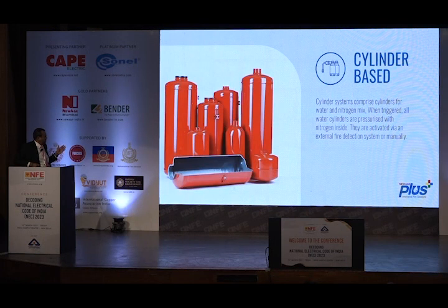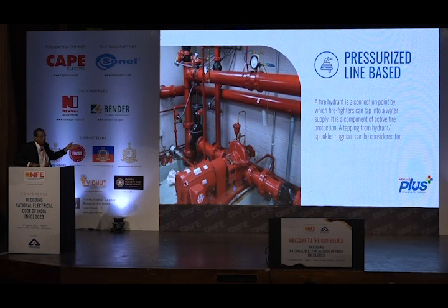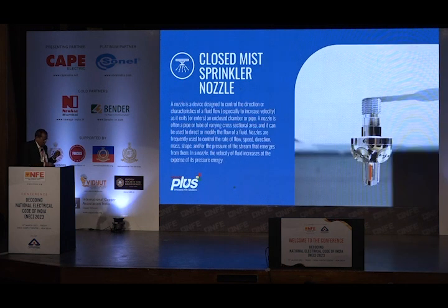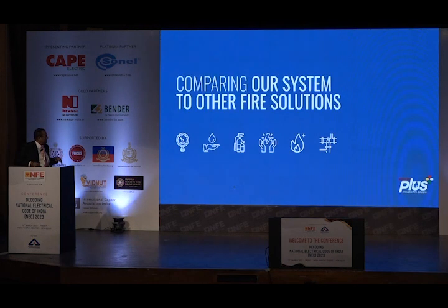We are using very standard cylinders; no PESO approved cylinder is required in this case. For the pressurized system, any pump in our hospitals or in the plant can be used. These kinds of nozzles give the mist. In a sprinkler you will see only one hole of 3/4 inch, and a huge amount of water comes out. Here there are multiple nozzles, and we can even have a bulb, which will burst and give you mist for fire extinguishing. We also have other accessories, like solenoid valves.